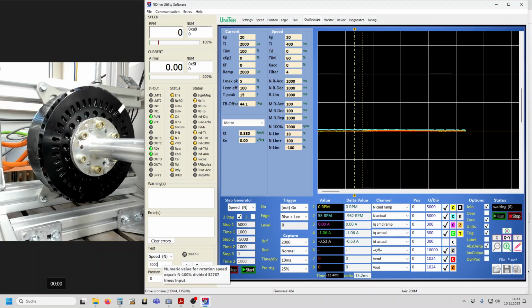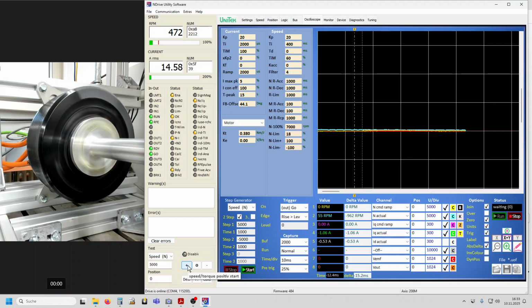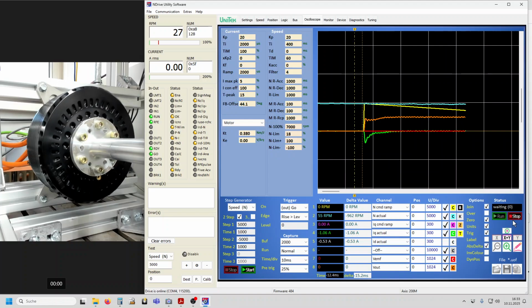We do not see much because the RPM speed was quite low. Now we go up to 1000 RPM while the drive is enabled. The RPM speed is roughly at 1000 RPM. It can be lower, it can be a bit higher. It doesn't matter. It's just that we need a high rotation during the enable process. You will hear a loud clicking noise. That is because just after the enabling process with torque 0 control, you will have a small AC current flow. In this case, about 67 ampere.